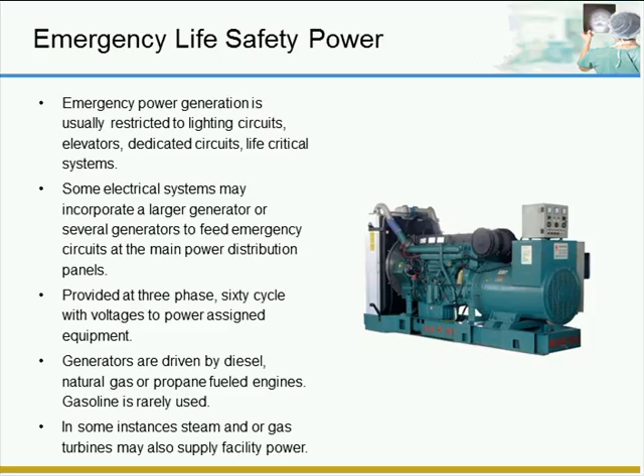One other item I'd like to add on that, Bill, is that management should research and be familiar with the location of the fuel supply for the emergency power source. The weekly testing of the generator will use fuel, requiring that the fuel supply be monitored and maintained at an adequate level. They should also review the potential for the fuel supply to become contaminated by water in a weather event that could send unexpected amounts of water from rain, runoff, flash flood, or tidal surges into the area where the fuel tank is located. Great point, Ken.